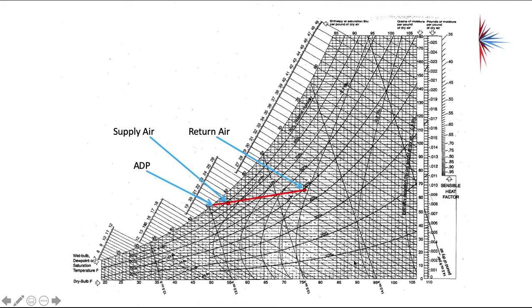We have our return air temperature here at about 77 degrees, and our supply air here at about 55.4 degrees. If you extend that line out to the scale on the left-hand side, or at the 100% humidity line, you can find the ADP by just extending that line out. That gives you the apparatus dew point — a lot easier than doing a lot of the math.